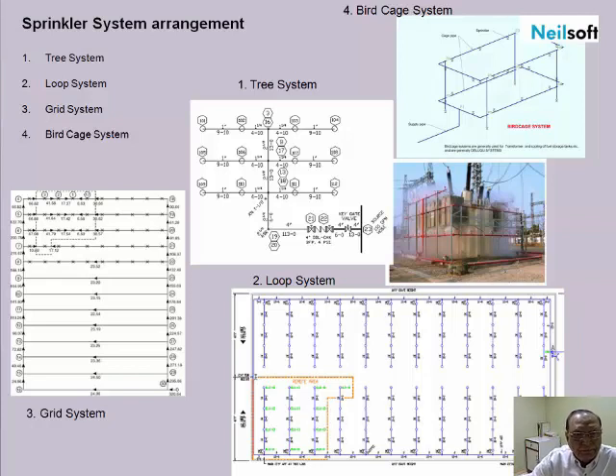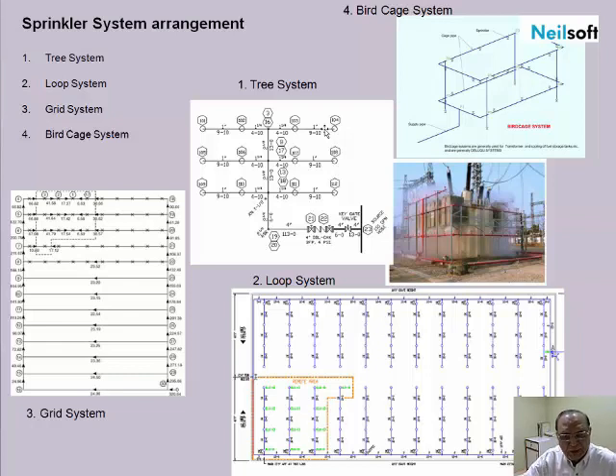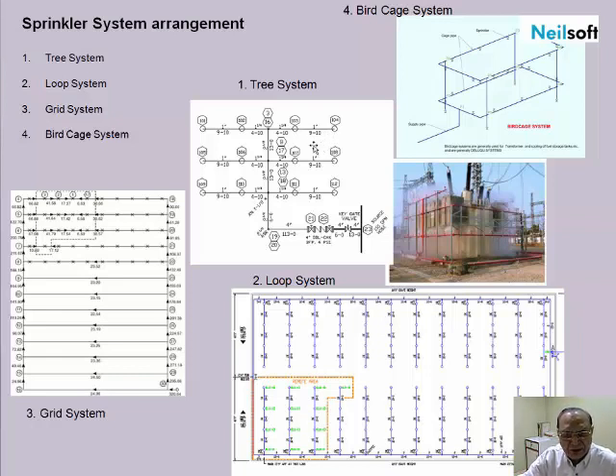How sprinklers are arranged in sprinkler systems: four types of sprinkler arrangements are generally used for firefighting system design. The first, as seen here, is the tree system. The tree system is like having a trunk, branches, and leaves — in the same way, we arrange our sprinklers in any direction, with the design restriction that any branch should not have more than 8 sprinklers.